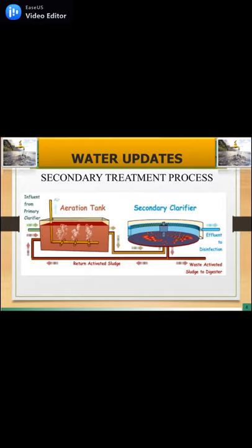Biological nitrification mainly takes place in this aeration tank. Nitrification is the process of converting ammonia in wastewater to nitrate using aerobic autotrophic bacteria. Nitrification is actually a two-step process for removing ammonia from wastewater using two different types of autotrophic bacteria that oxidize ammonia to nitrite and then oxidize nitrite to nitrate. Biological nitrification systems are designed to completely convert all ammonia to nitrate.